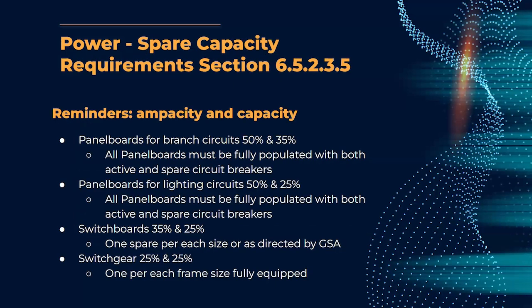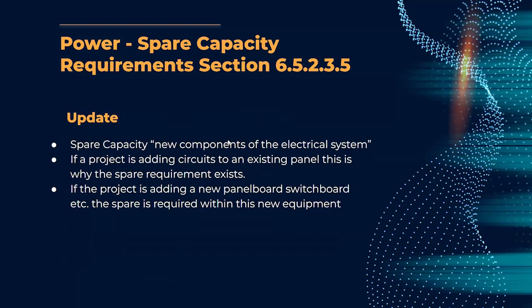Spare capacity and ampacity. I won't read all of the bullets here, but I want to point out that GSA's requirements are a bit higher than industry standard. You can see the 50% there on the panel boards. I encourage you to familiarize yourself with this. The intent here is we have these facilities in our inventory for a very long time, and this provides resiliency and flexibility for us to do what we need to do over the years while we own these buildings.